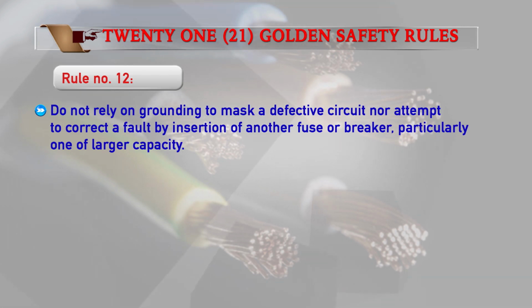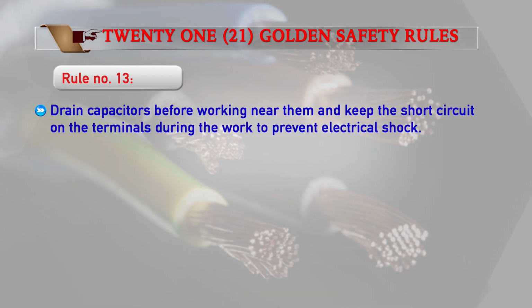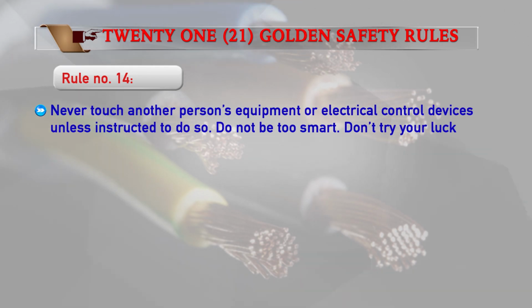Rule number 12: do not rely on grounding to mask a defective circuit, nor attempt to correct a fault by insertion of another fuse or breaker, particularly one of larger capacity. Rule number 13: drain capacitors before working near them and keep the short circuit on the terminals during work to prevent electrical shock. Rule number 14: never touch another person's equipment or electrical control devices unless instructed to do so.